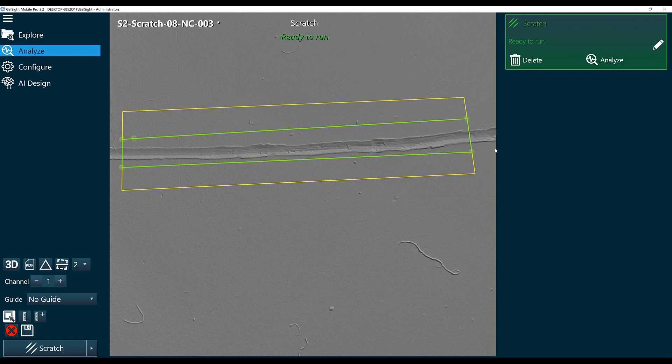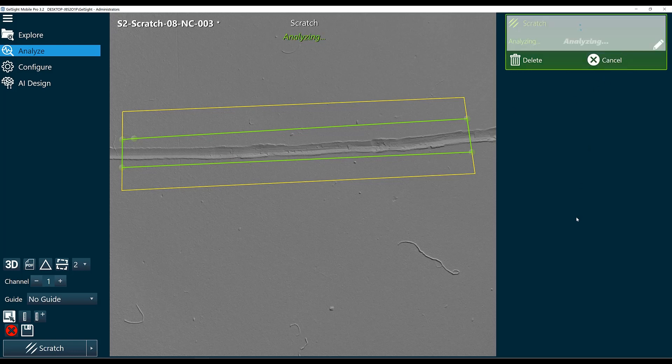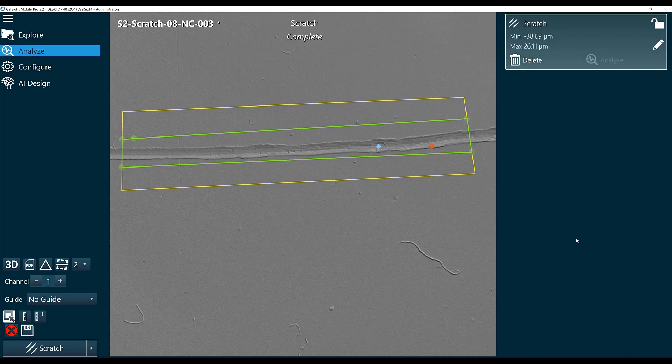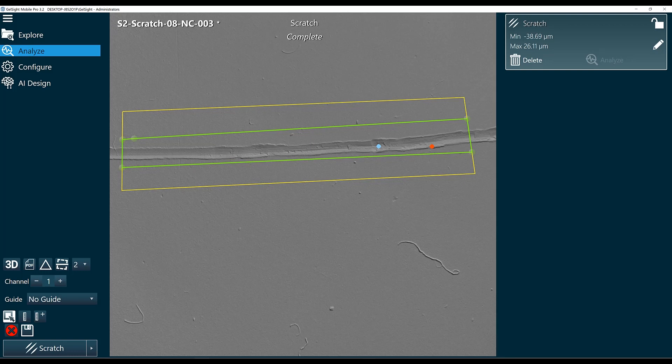And now our scratch will not be included in the definition of our reference plane. And we can go ahead and click analyze. And the output of about 39 micron is that blue dot here is the deepest point within our scratch. And from that we can just generate a quick PDF report.